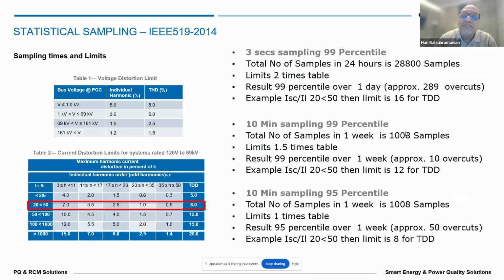So as I said, out of the total number of samples, 28,800, it can cross the limits 289 times. So approximately, there is a leverage. In other words, out of 28,800 samples, we can cross the limits roughly 289 times. In the same way, for 10-minute values over a weekly period, you have 1,008 samples per parameter, and you could have 10 overcuts for the 99th percentile and 50 overcuts for the 95th percentile.